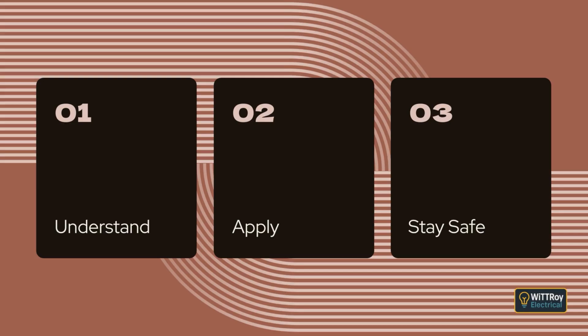Section 1.6, Design of an Electrical Installation, Clause 1.6.1, General. When you design an electrical installation, it must achieve 5 main objectives. First, it must protect people, animals, and property from harm. Second, it must work properly for whatever purpose it is intended to serve. Third, it must connect safely to the supply, whether that supply comes from the electricity distributor or another source, and it must remain safe during normal operation and during a fault.